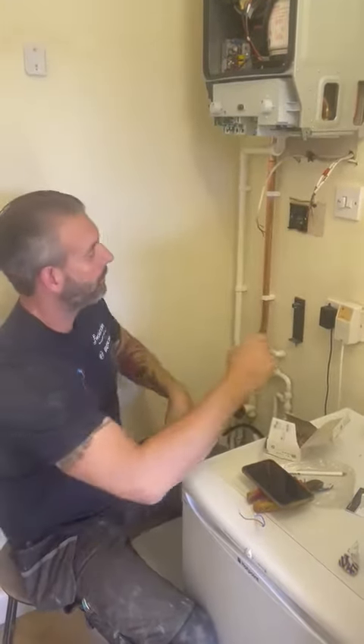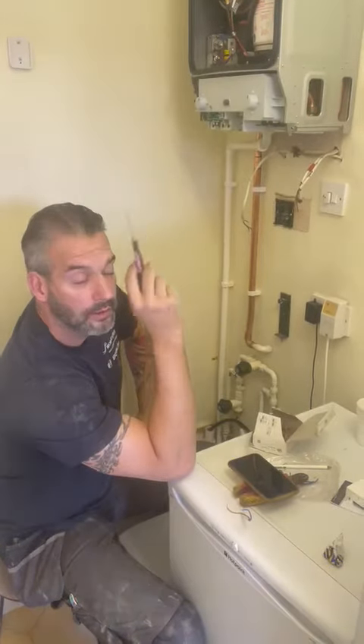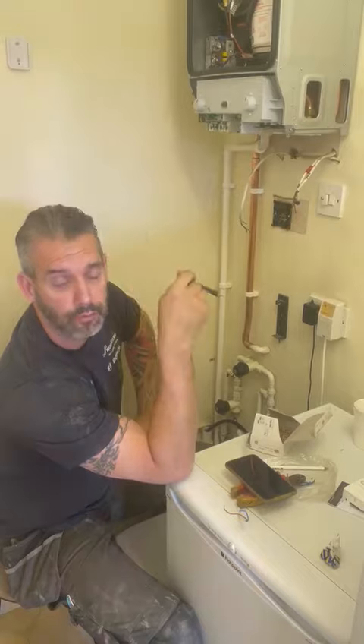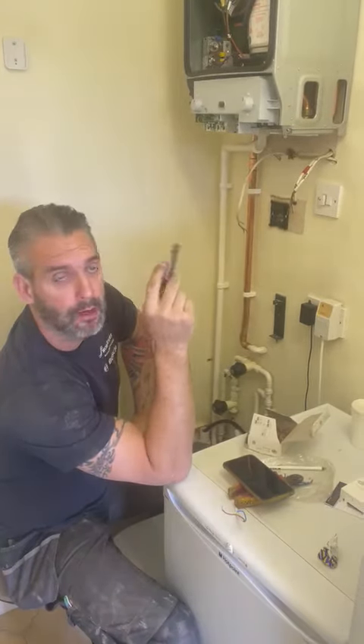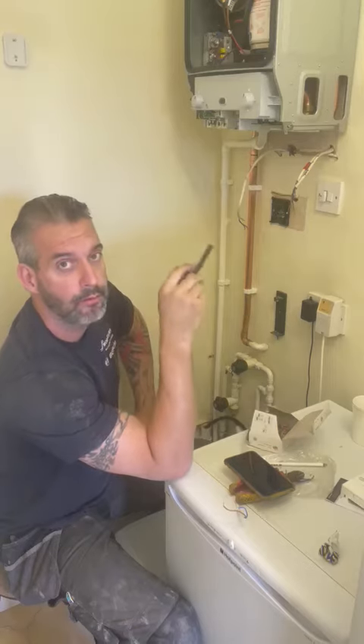Right, that's our whole walk-off. So I basically look at the new boiler — customer decided to change all the controls: digital programmer, room thermostat, motorized valves, new pump — all the controls changed, really. Really future-proofing on this one.